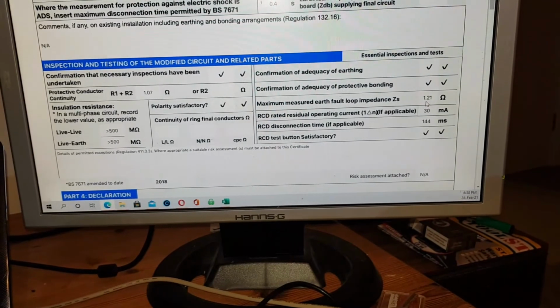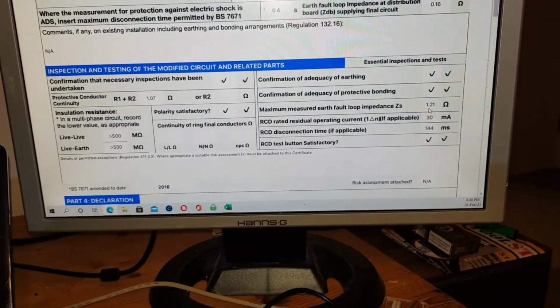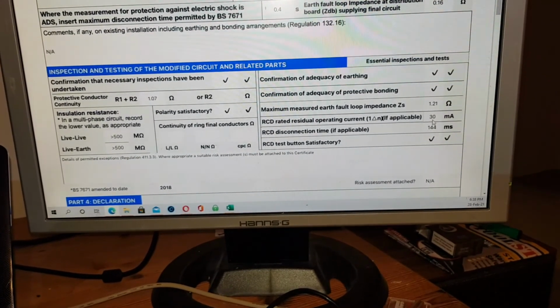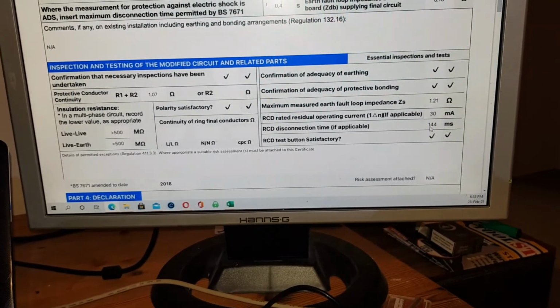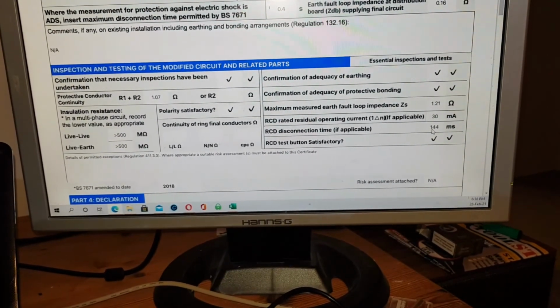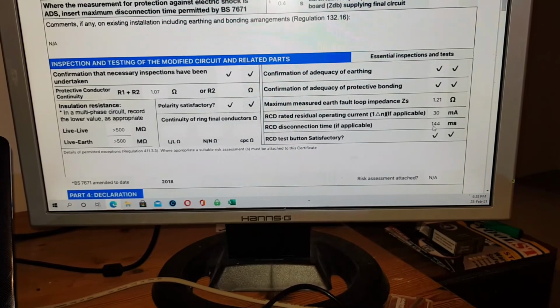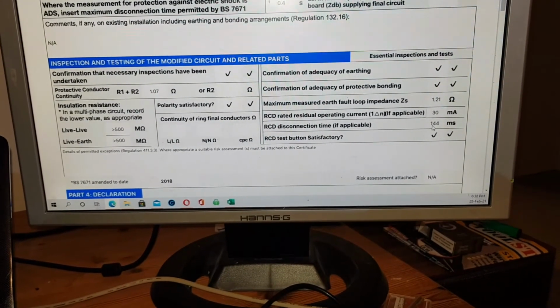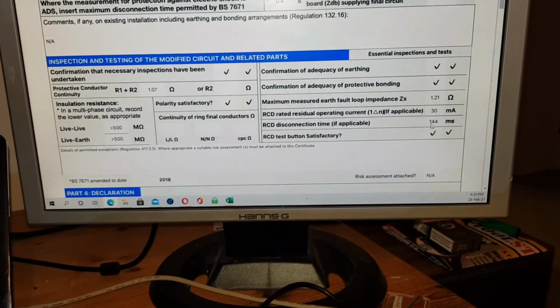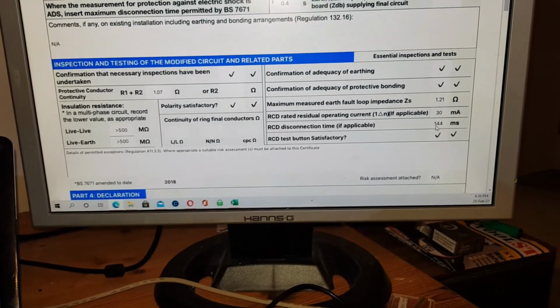Earth loop impedance 1.2 on the finished circuit, the highest reading out of the 3 lights. RCD disconnection time, whilst it's a pass at 144, is relatively high. I mean, most of the ones I go to are sort of 30 milliseconds.